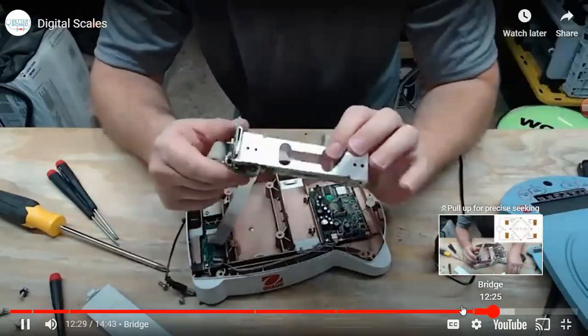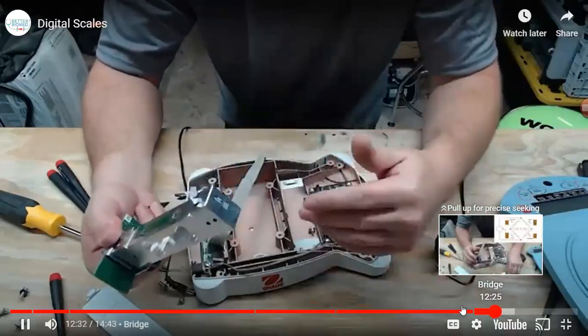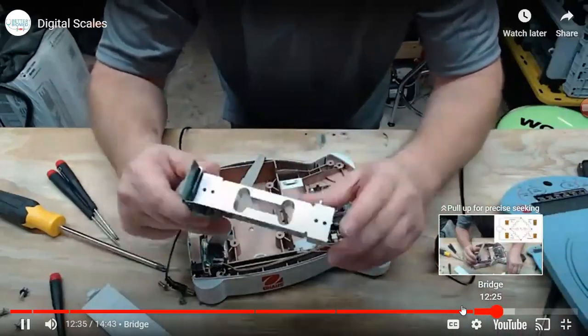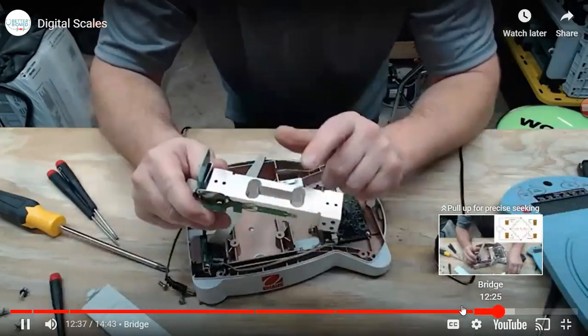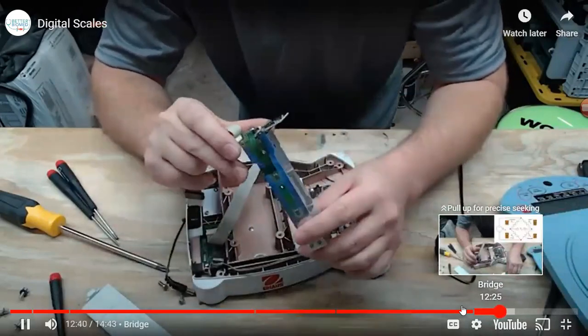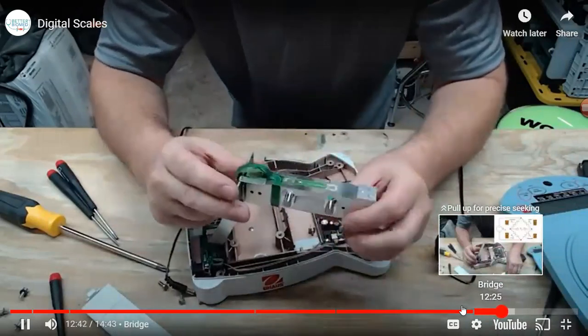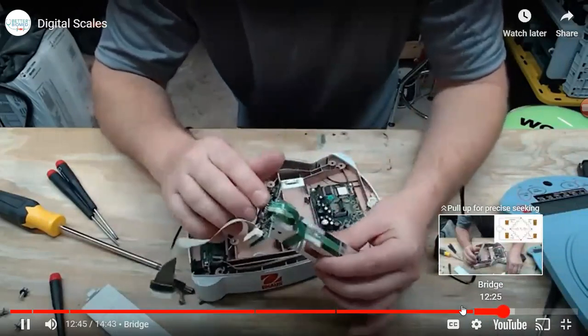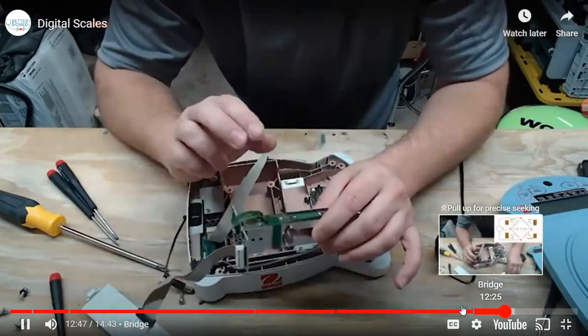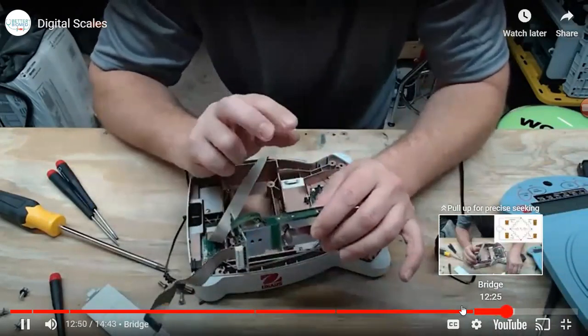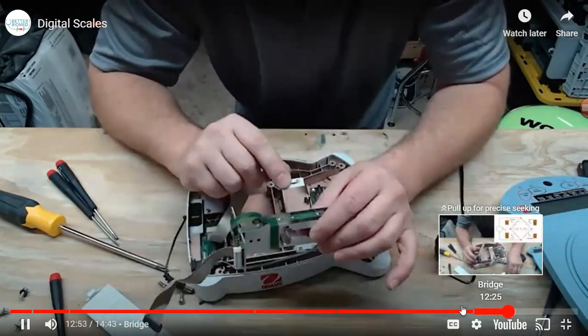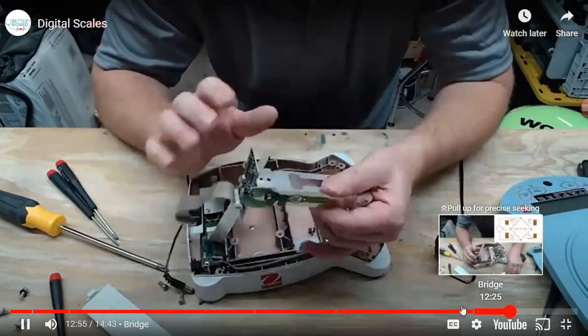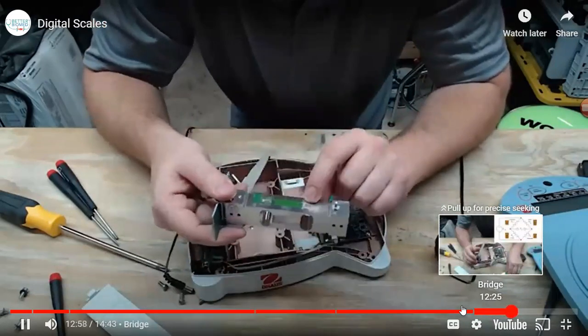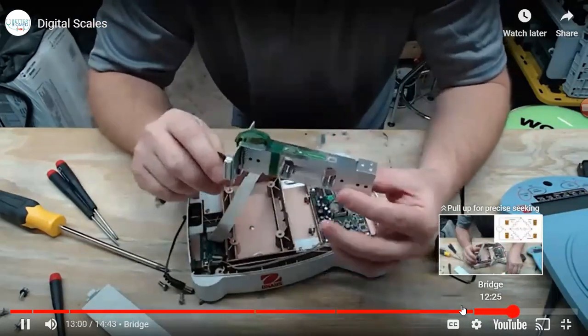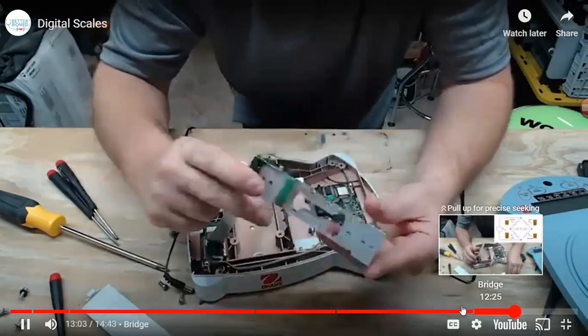Yeah. It is a full bridge, just like a full bridge rectifier that you find for AC to DC conversion. This is a full bridge because there's 4 strain gauges. This is actually very interesting. So you can technically measure these with ohms to see if they were close in tolerance. If you have one of these little strain gauges that's got a much larger ohms value than the others, then that's going to be your problem.